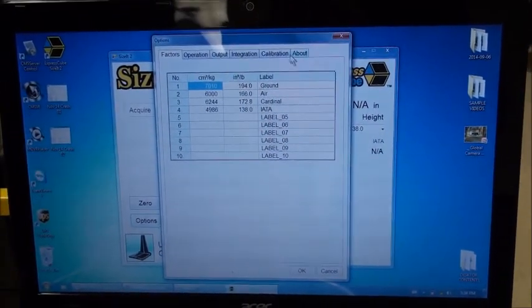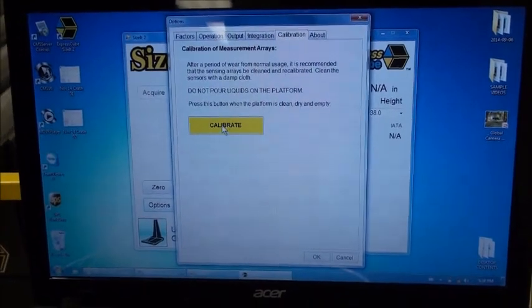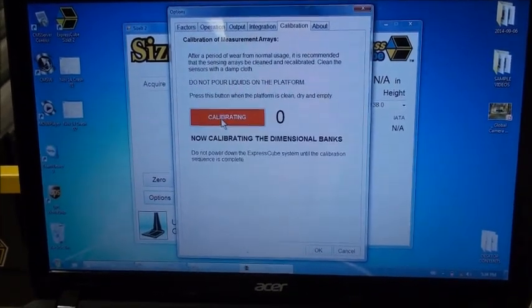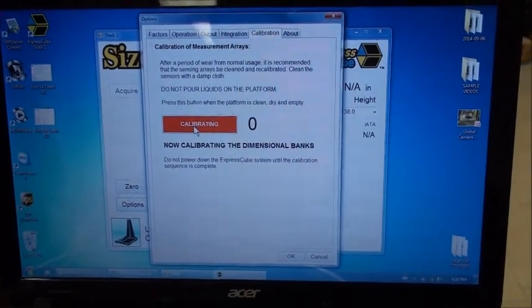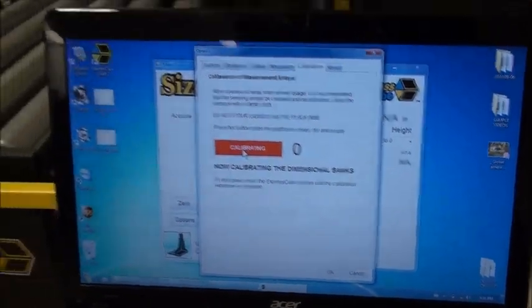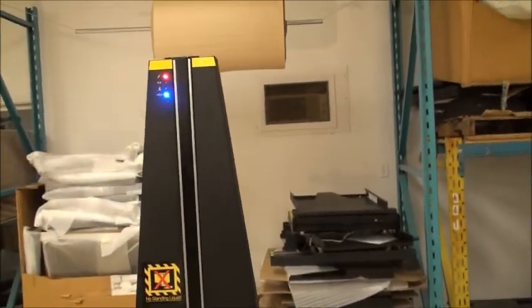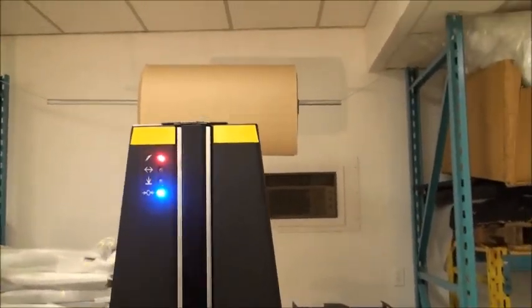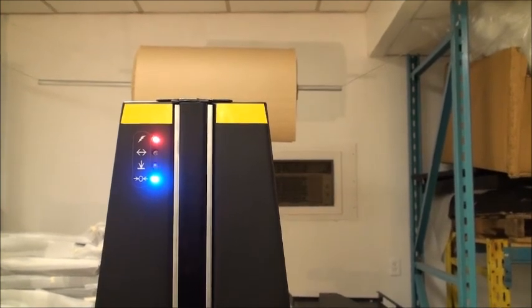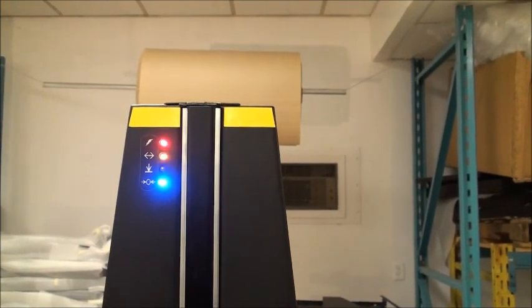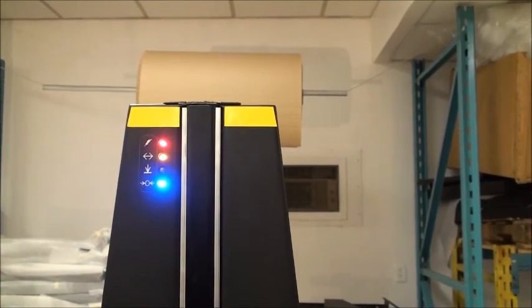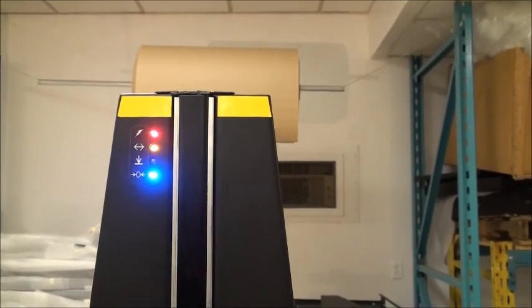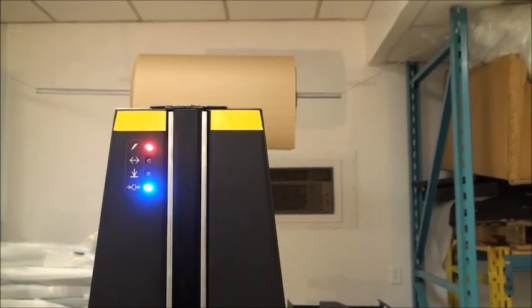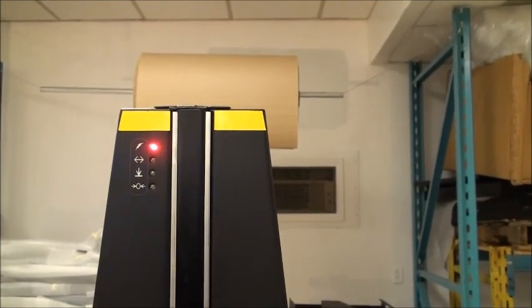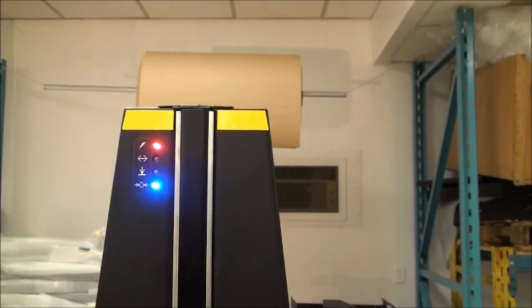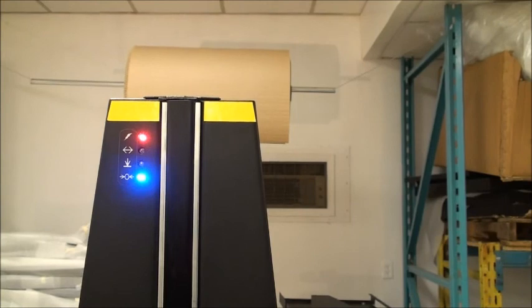I'm going here now to calibration, and we push the button for calibrate. Now you can see this thing says it's calibrating. If we pan up here to the machine, you can actually monitor its progress by looking at the LEDs. And each of the LEDs flashing represents a bank. And there are 4 banks. So you'll see 4 different cycles of flashing. And when the cycle of flashing is finished, the unit is calibrated.